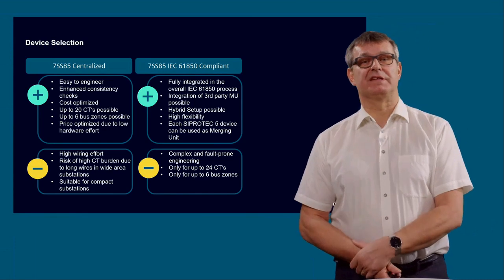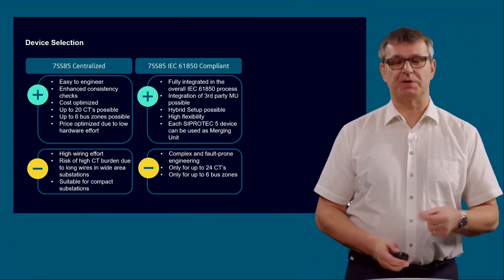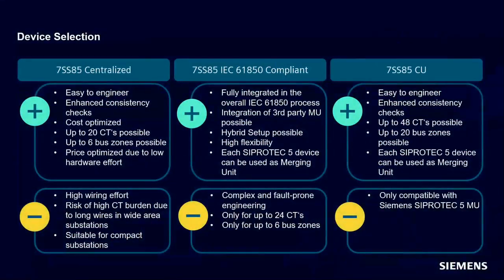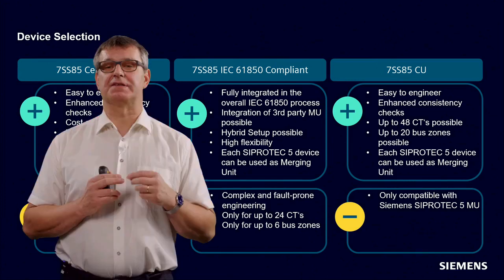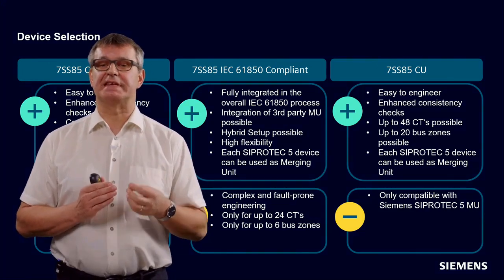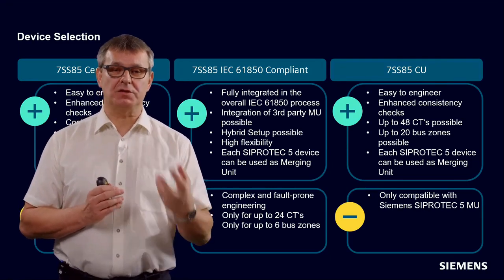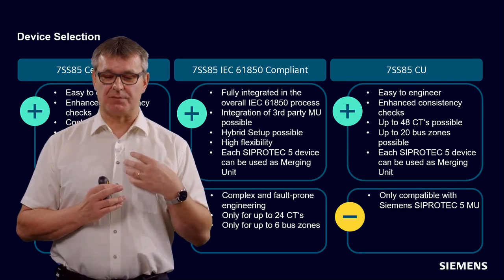Let's come to the 7SS85 CU, the fully distributed busbar protection. It's very easy to engineer, especially in contrast to the IEC 61850 compliant solution. You can also use very enhanced consistency checks. Let's come in the same step to the disadvantage: you can't use third-party merging units for the 7SS85 CU solution. This comes with these enhanced consistency checks, which are of course not possible if we are using a device from a third party.